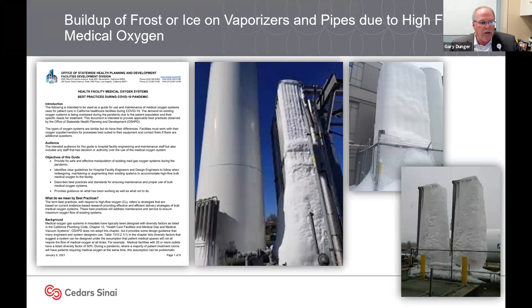One of the byproducts of increased liquid oxygen flow is the vaporizer's inability to keep up and facilitate the phase shift of liquid oxygen from a liquid to a gas. This became very problematic and prompted OSHPD to issue the best practice you see over on the left.